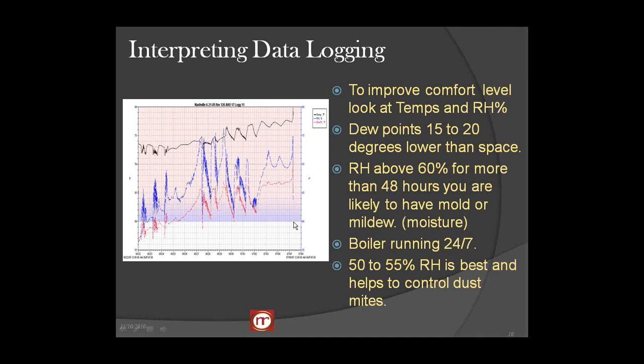And I can also tell you, according to EPA, that if the relative humidity is above 60% for a period of more than 48 hours, you're likely to have mold or mildew. We refer to that as a moisture problem because that's exactly what it is, and mold seems to panic people. Now, this particular school is a hot water, chill water school, and if you notice the 60% alarm level, and look at the blue, for the entire test period we were in alarm. So there's a lot of issues here, and I can also tell you that with dehumidification, this boiler is running 24/7 and not dehumidifying.